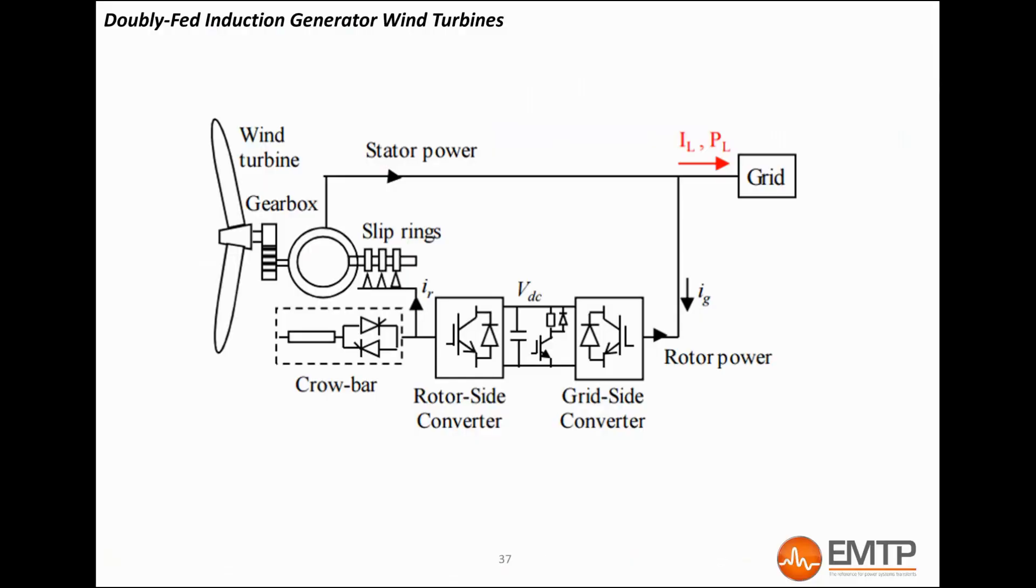Doubly fed induction generator wind turbines, which are generally called DFIG wind turbines, have the stator of an induction generator directly connected to the grid and the wound rotor of this machine connected to the grid through an AC-DC-AC converter. This converter system consists of two voltage source converters, the rotor-side converter and the grid-side converter. Although not shown in this figure, a line inductor called choke filter and a shunt harmonic AC filter are used on the grid-side converter to improve power quality.